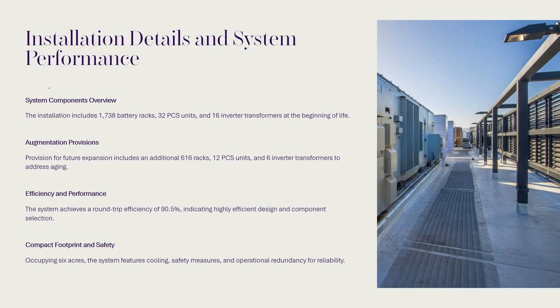System component overview: the installation includes 1738 battery racks, 32 PCS units, and 16 inverter transformers at beginning of life, with augmentation provisions for future expansion including an additional 616 racks, 12 PCS units, and 6 inverter transformers to address aging.